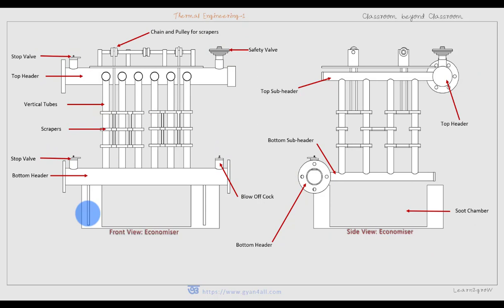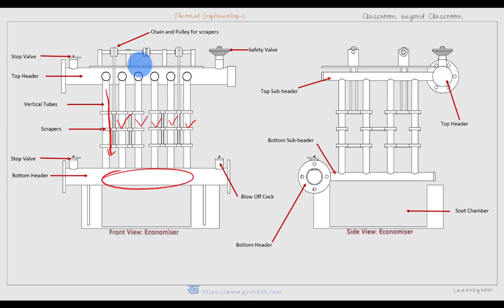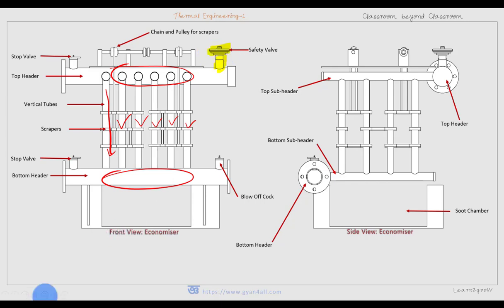To summarize: this type is called the Green's economizer, which consists of a group of vertical cast iron tubes fitted between the top and bottom header. For safety against high pressure, a safety valve is mounted on the top header. Like a boiler, it also has a blow-off valve fitted at the bottom to discharge sediments collected at the bottom of the economizer. Scrapers are provided on the tubes to remove the soot of flue gas deposited on the tubes.